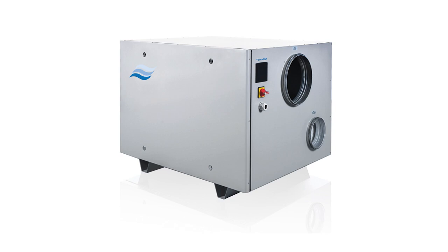This is because in a desiccant dehum, a heater is used to blow hot air through a section of the desiccant rotor. Now, this removes the absorbed water from the desiccant rotor and blows it outside via ducting. Now, the residual heat from this rotor regeneration process will add even more heat to the process airflow than is already happening from the thermodynamic process. So both types of dehum will add heat when drying, but the desiccant unit can add significantly more.